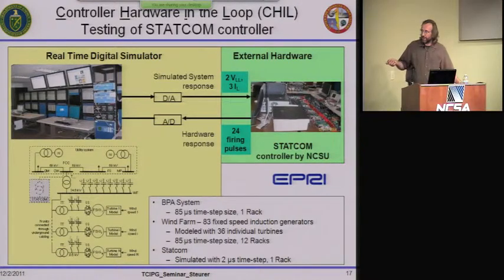We started out aiming to model as many generators as we could using our racks, and we were able to get 36 individual turbines onto 12 racks. Each turbine included the wind turbine itself, the gear system, and the fixed speed induction generator, which had to be modeled with 2 generator models because they are pole-switched machines, 4 to 6 pole, and there was no pole-switchable machine model in RTDS, so we used two models to switch between. We also had the soft starter, the local cap bank, and the step-up transformer, all modeled in the RTDS. That's why you end up with 36.